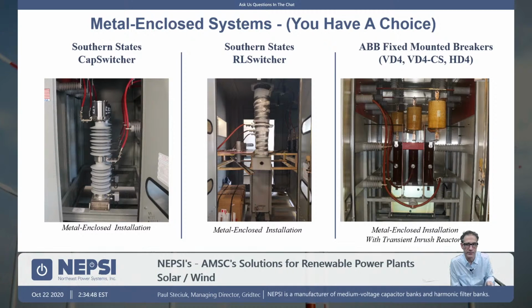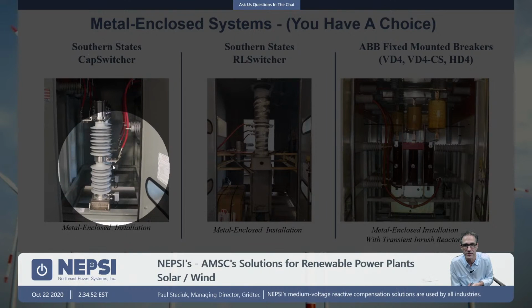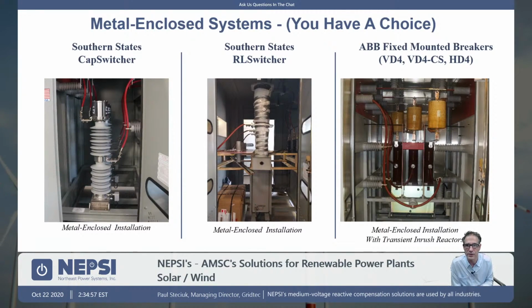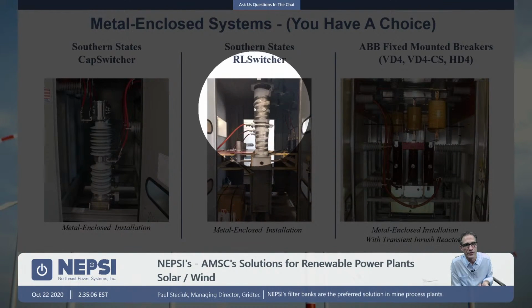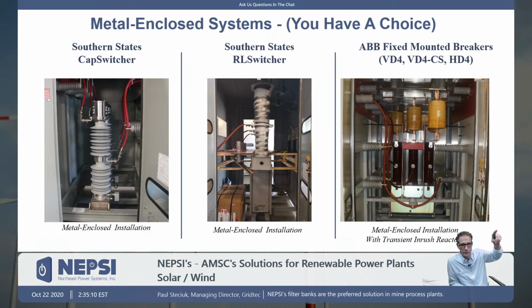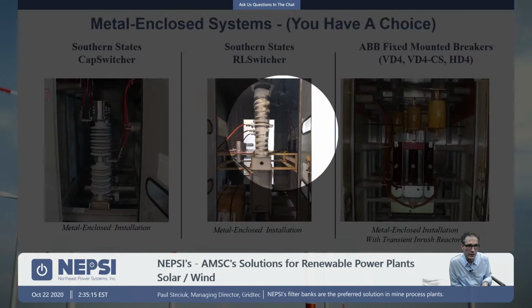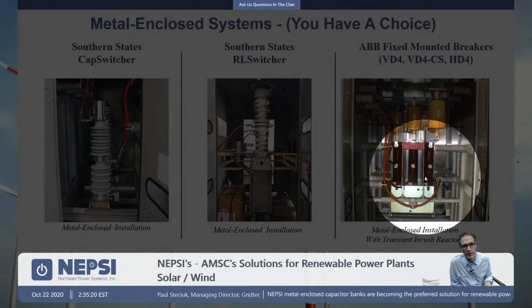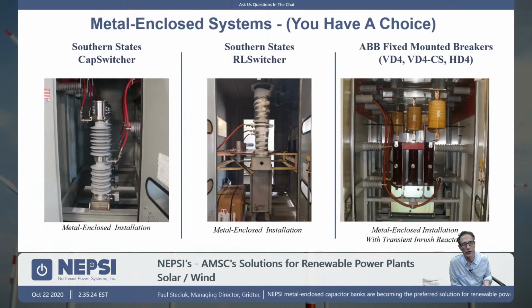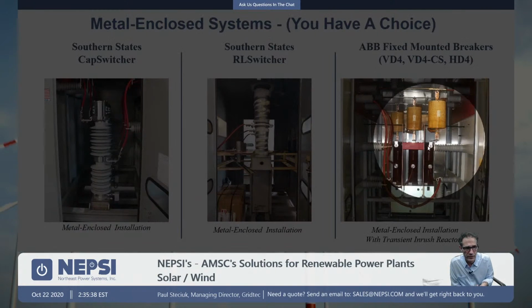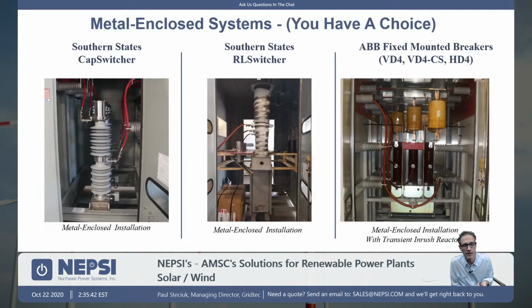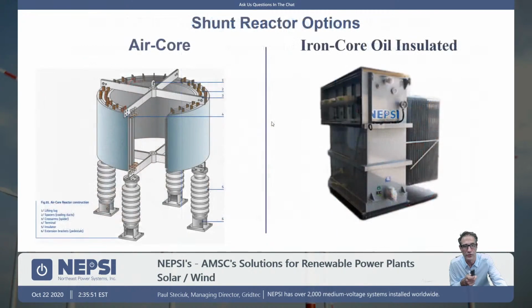On the inside, the enclosure, we can park a Southern States cap switcher in there. We do it very often. Some people in the industry prefer that Southern States cap switcher. We can put that inside our gear. It works very well. This is the RL switcher in our gear here. You can see one of the major issues here is it's very tall. So we have to do a bump up in the enclosure, and that becomes a difficult thing. We can also use the breakers, and this is really something to plan on, is that there are some advantages of using the VD4 and the VD4CS from a cost standpoint and from a lead time standpoint, and also because we can eliminate that upstream feeder breaker. So incidentally, what you're looking at here is a VD4 breaker, and we've got transient inrush reactors here. If it were a VD4CS, one that was doing synchronous closing, it would not have those reactors, because we're doing synchronous closing, no reactor.